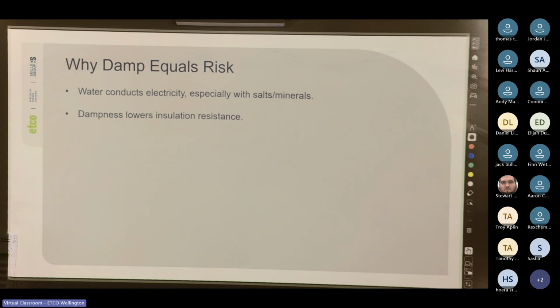So the dampness lowers our insulation resistance. If a cable is damp, you can insulation resistance test it. You can leave it on, say, 500 volts for an extended period, and it can actually dry out the cable. It is not recommended if you can replace it. But it can clean out waterlogged cables, especially if it's been in a conduit that's flooded.